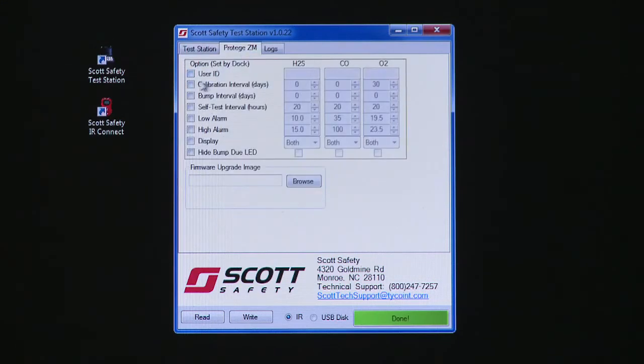On the Protege ZM tab of the application, you can change the settings to be stored on the monitors during testing. Settings include the calibration and bump intervals, self-test interval, the display settings, and the low and high alarm settings. Items marked with a check mark will be programmed into the monitors whenever they are tested. This is a convenient way to ensure your monitors are always programmed with the latest settings. Click the Write button to save these settings on the test station.